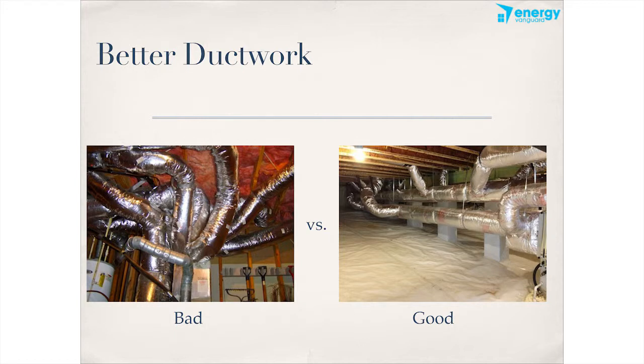This system is not designed. That's a system where the installer showed up with all their bags of ductwork. This is flex duct, and it comes in a bag of 25-foot lengths. And they showed up with all the bags of ductwork in the back of the truck, and they bring them inside, and they just start attaching them and dragging them to the places where they need to go. And there's no thought here about whether you're going to get enough airflow in the different rooms or not. It would be a miracle if something like this actually delivered the right amount of air to each room.